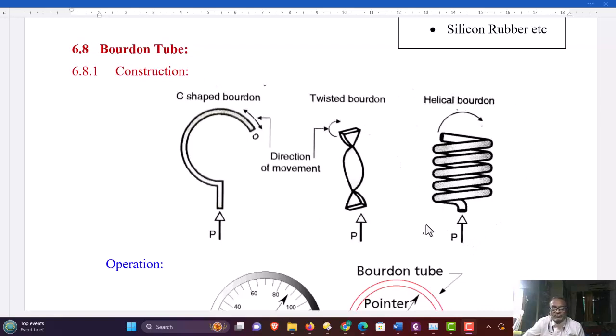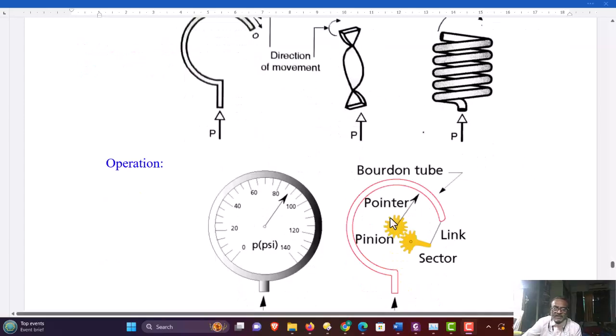The third figure shows a helical Bourdon tube. Whenever pressure is applied to this tube, the helical tube will expand and it will be uncoiled. So the remote end will be uncoiled and it is displaced due to the application of pressure, and this displacement can be used for measuring the applied pressure.